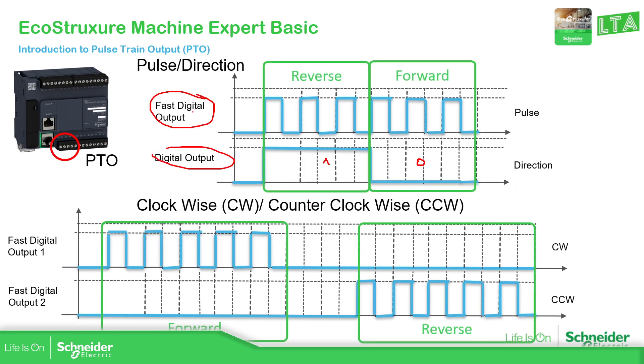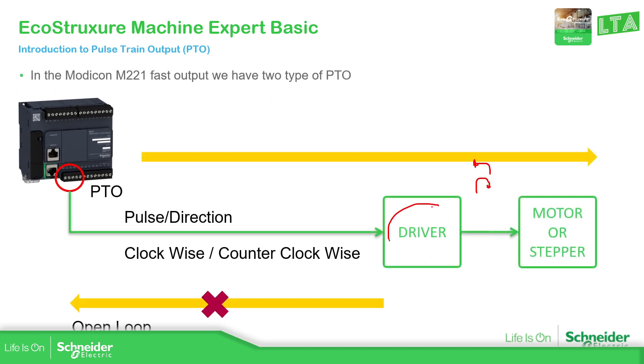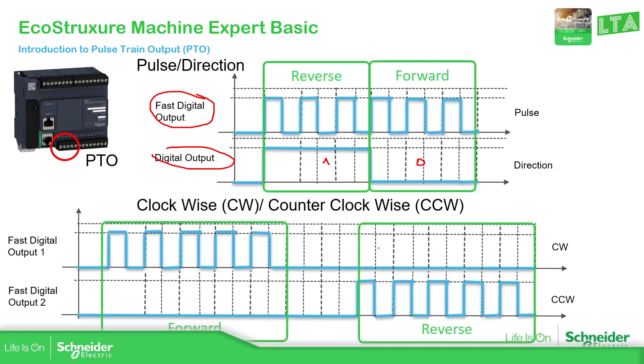Comparing this to the clockwise/counter-clockwise configuration: you can see in the graph that we have fast digital output one and fast digital output two. Depending on which fast output carries the pulses, the driver will understand whether to go forward or reverse. One disadvantage compared to pulse-direction is that here we need to use two digital outputs instead of one, so we are limited by the amount of PTO outputs available on the controller.